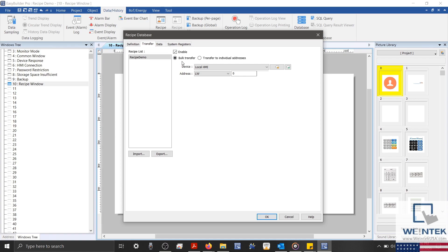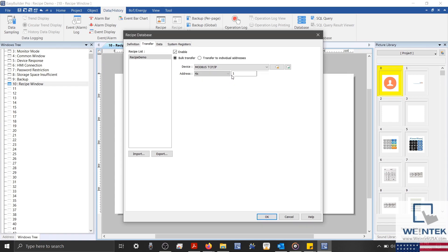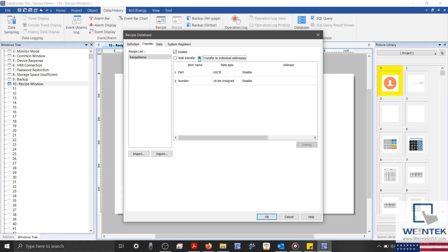To define a transfer, we'll first need to enable this feature. Then, we can either define a bulk transfer, which will transfer a selected row of data to a sequential list of registers within the PLC, or we can transfer each address individually at our discretion. Let's configure both transfers to separate addresses.